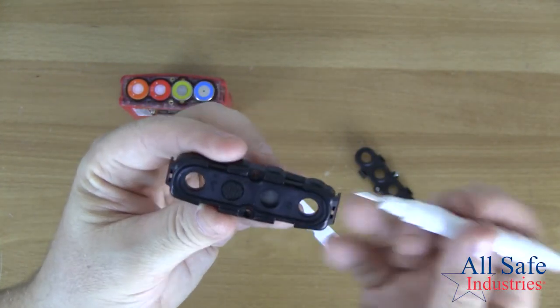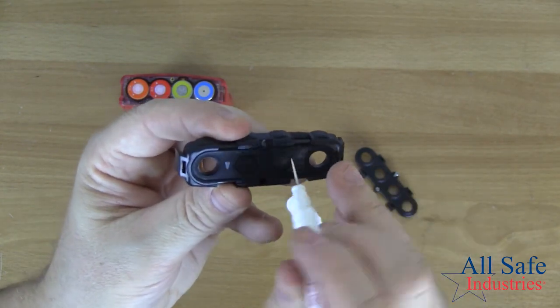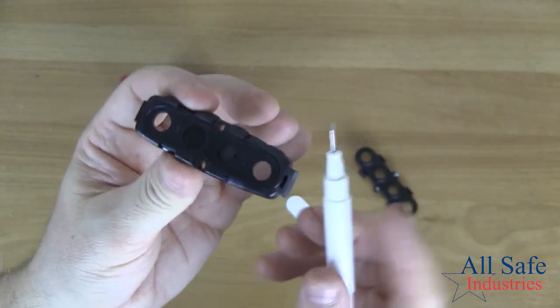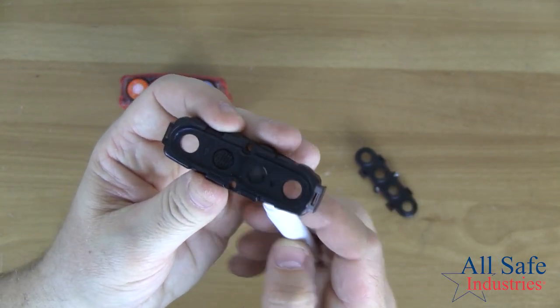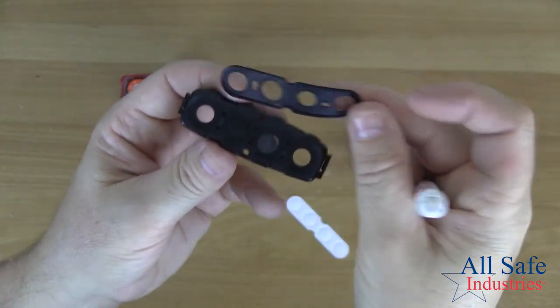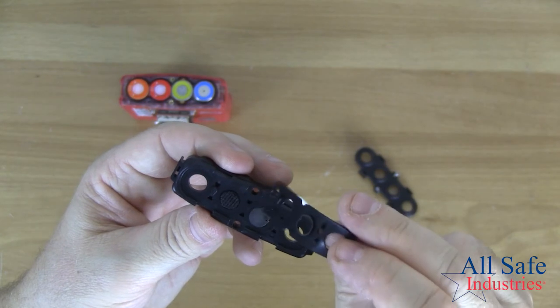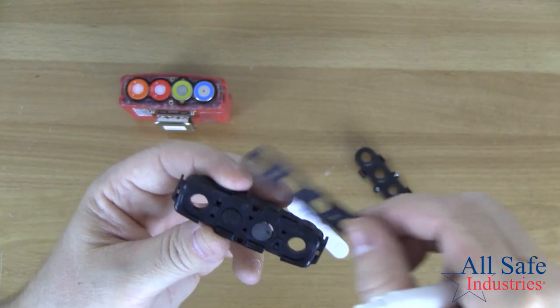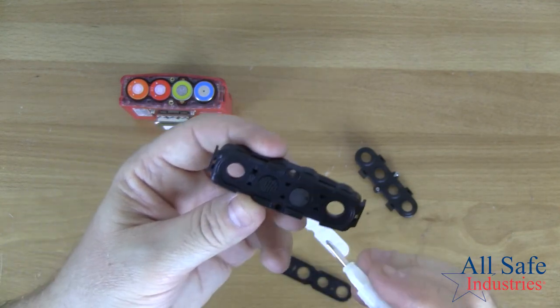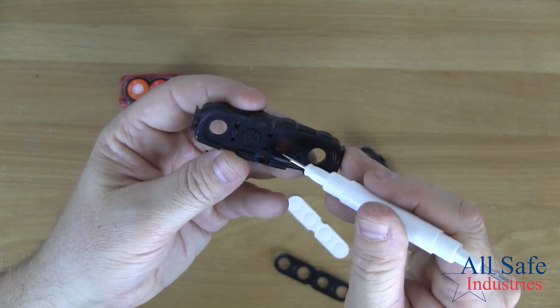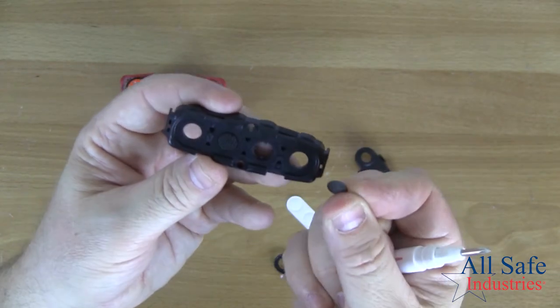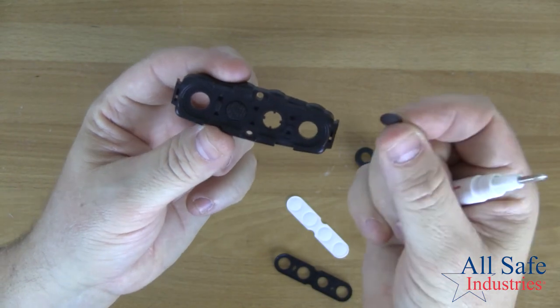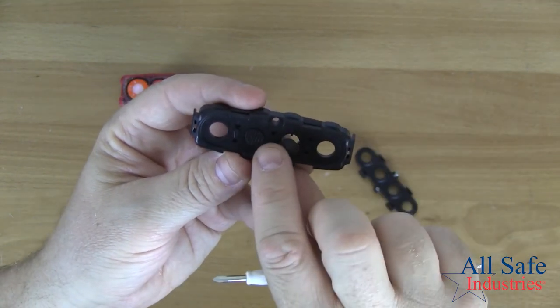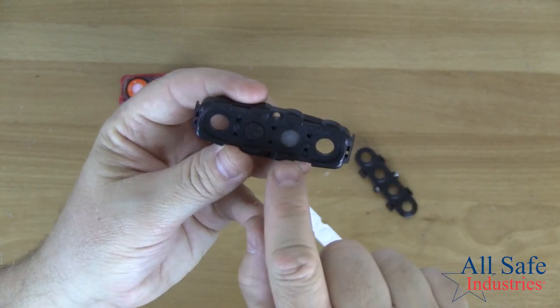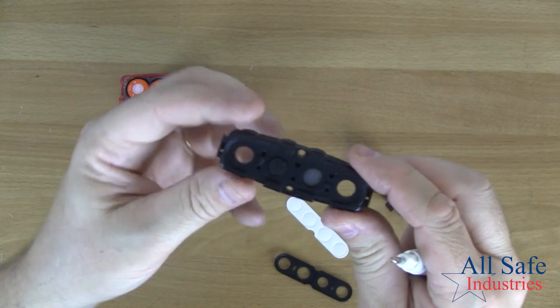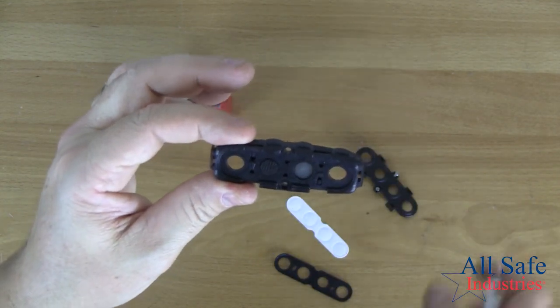Then we also have a hydrogen sulfide filter. I'm going to pop that guy out. And this helps protect, I'm actually going to push it up from the bottom. I'm sorry, there's actually a gasket in here too. So there's our gasket that sits in between our hydrophobic filter and the sensor retainer. And then here is the little H2S filter that I mentioned. Now my H2S filter actually needs to be changed. These should be white. And you can see how this filter has reacted to enough hydrogen sulfide gas. This sits right over the LEL sensor, which keeps some of the hydrogen sulfide off the LEL sensor, which can degrade the life of the sensor.